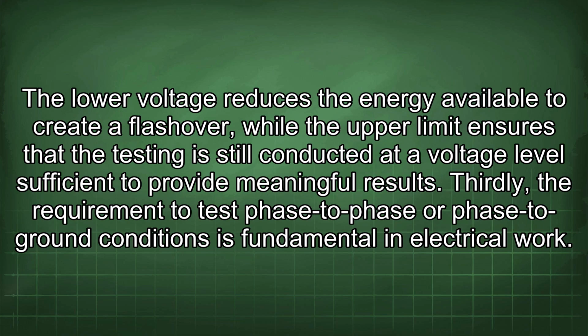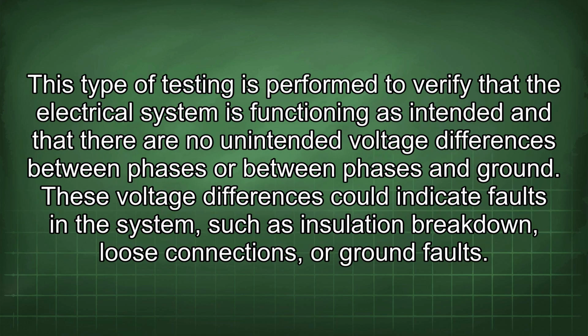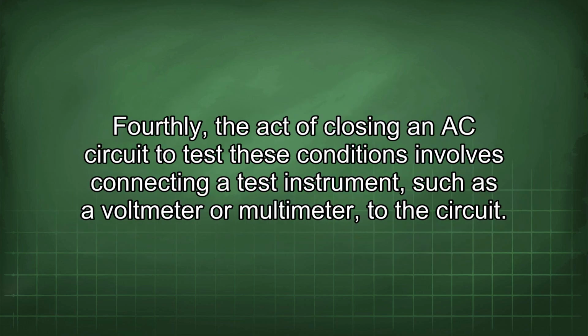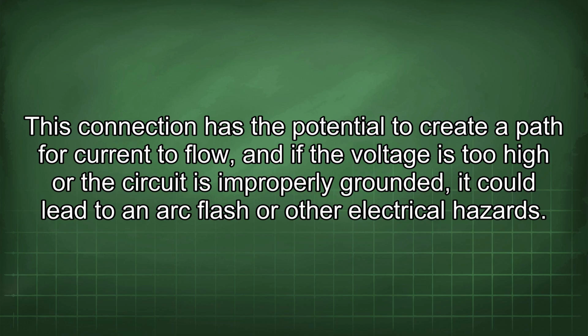Thirdly, the requirement to test phase-to-phase or phase-to-ground conditions is fundamental in electrical work. This type of testing is performed to verify that the electrical system is functioning as intended and that there are no unintended voltage differences between phases or between phases and ground. These voltage differences could indicate faults in the system, such as insulation breakdown, loose connections, or ground faults. Fourthly, the act of closing an AC circuit to test these conditions involves connecting a test instrument, such as a voltmeter or multimeter, to the circuit. This connection has the potential to create a path for current to flow, and if the voltage is too high or the circuit is improperly grounded, it could lead to an arc flash or other electrical hazards.